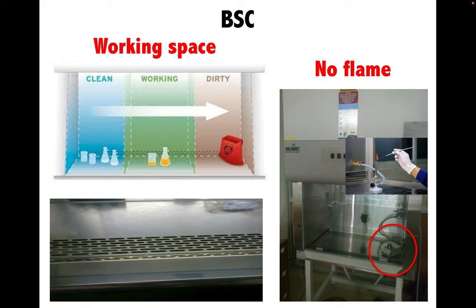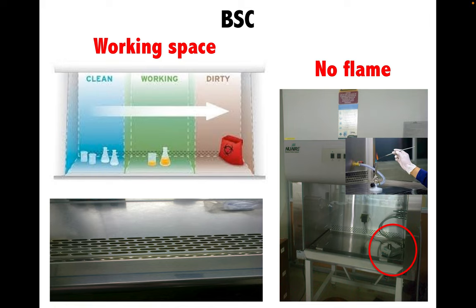To operate the BSC safely, you need to assign which area is the clean zone, working zone, and dirty zone. Do not block the inflow air by placing items on the inlet space. Very importantly, do not use heat or flame inside the BSC, as it interferes with the laminar flow and can potentially damage the HEPA filter. Like the fume hood, do not store items inside the BSC.